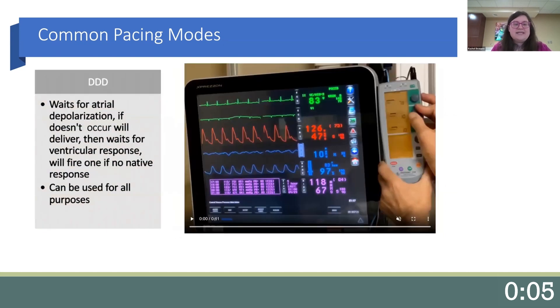In DDD, both chambers are being sensed and paced. In this mode, if atrial depolarization doesn't occur, it will wait for a sensed ventricular depolarization. If neither of these events occur, it will deliver energy to all chambers. Due to this, DDD can be used in nearly all cases.